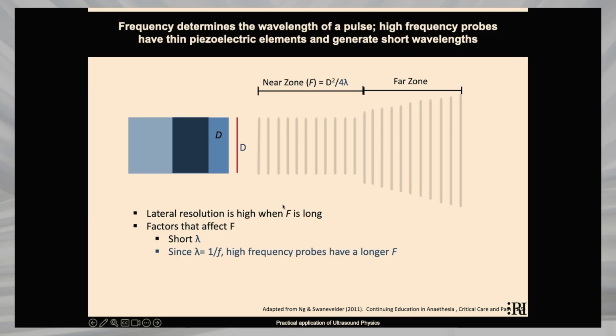Now, the near zone is where the beam is parallel, all the sound waves are running in parallel. When they pass beyond that point, they will diverge, and the information that you'll receive from here will be distorted, and you'll get lots of scatter information which will distort your image. So the best image you will get will be in this near zone. And having a high frequency probe has two advantages. It gives you better lateral resolution, and it will give you more of a near zone. The higher the frequency, the better the near zone.